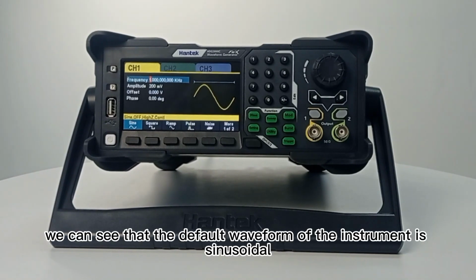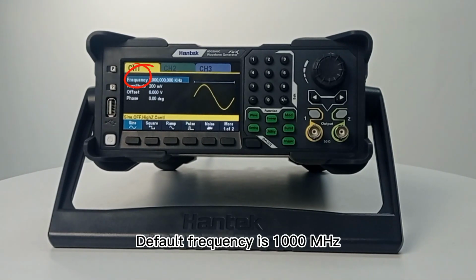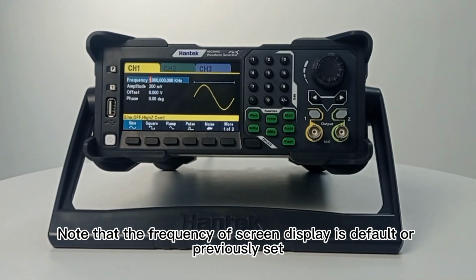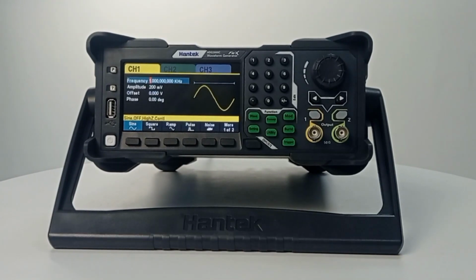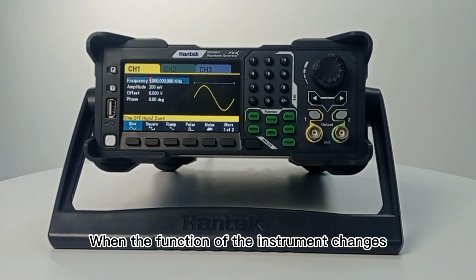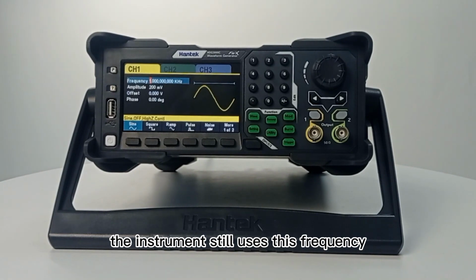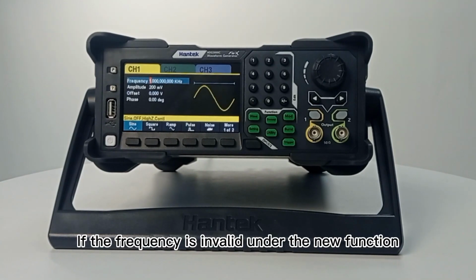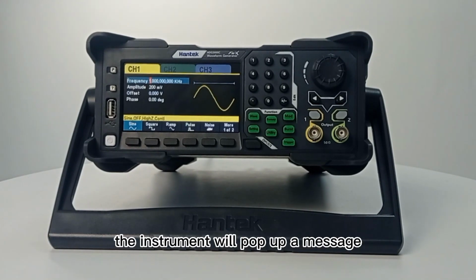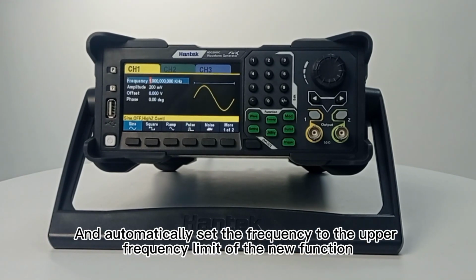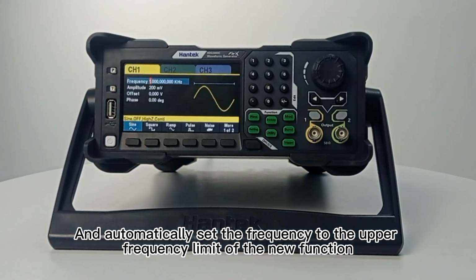On power on, we can see that the default waveform of the instrument is sinusoidal. Default frequency is 1 kHz. Note that the frequency on the screen display is the default or previously set. When the function of the instrument changes, the instrument still uses this frequency. If the frequency is invalid under the new function, the instrument will pop up a message and automatically set the frequency to the upper frequency limit of the new function.